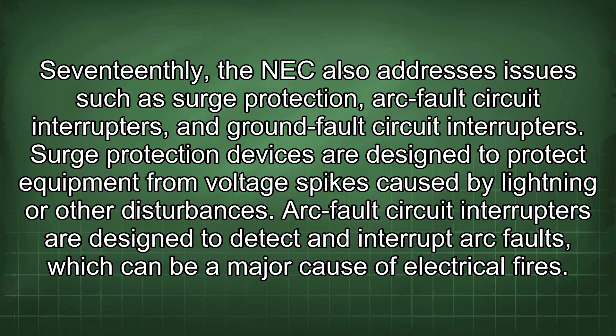The NEC also addresses issues such as surge protection, arc fault circuit interrupters, and ground fault circuit interrupters. Surge protection devices are designed to protect equipment from voltage spikes caused by lightning or other disturbances. Arc fault circuit interrupters are designed to detect and interrupt arc faults, which can be a major cause of electrical fires. Ground fault circuit interrupters are designed to protect people from electric shock by detecting and interrupting ground faults.